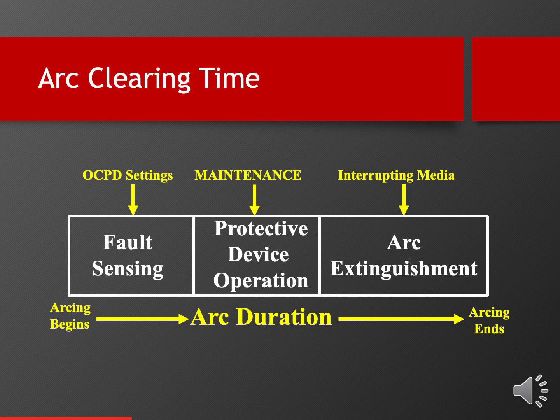And the third element of the arc is the arc extinguishment element, and that has mostly to do with the interrupting media. In other words, whether it uses oil to interrupt the current flow or gas to interrupt the current flow, how does it actually make the arc extinguish? Normally you can't impact that too much, but you certainly can impact the first two. Let's go to the next slide.